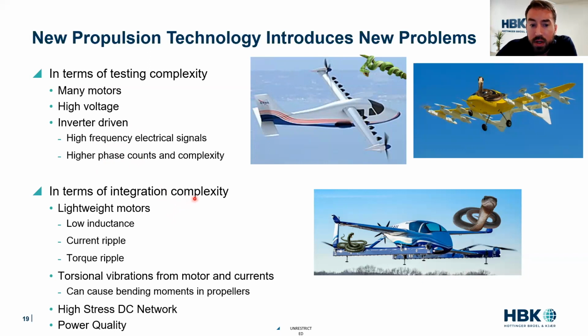In terms of integration complexity, for weight purposes there are a lot of lightweight motors, which means low inductance, which means current ripple, which means a lot of torsional vibration or torque ripple at the shaft. These torsional vibrations cause bending moments in propellers, so the electrical system has a direct effect on the mechanical system.